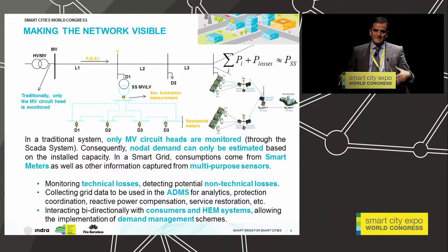At the same time, we now have the capability to incorporate sensors in the network, not only in the demand, but also in the secondary substation, along the medium voltage line, along the low voltage line. This gives us the possibility to monitor technical losses, detect potential fraud or non-technical losses, collect grid data to feed the distribution management system, or ADMS—Advanced Distribution Management System—and the ability to interact with consumption.